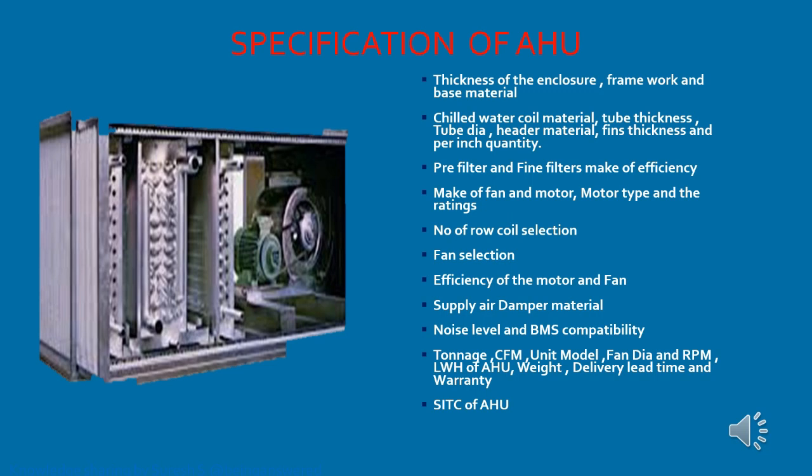Let us see what specifications we need to check for an AHU. First: thickness of the enclosure, framework and base material. Next: chilled water coil material, tube thickness, tube diameter, header material, fin thickness, and fins per inch quantity. Also check pre-filter and fine filter make and efficiency, fan and motor make, motor type and ratings, number of rows in coil selection, fan selection, and efficiency of motor and fan.